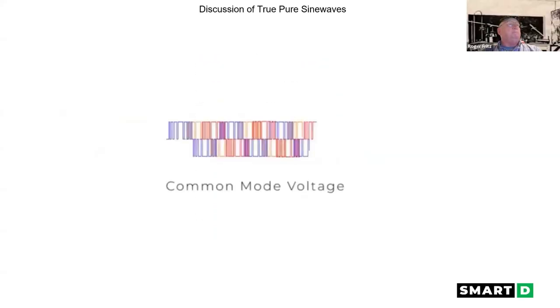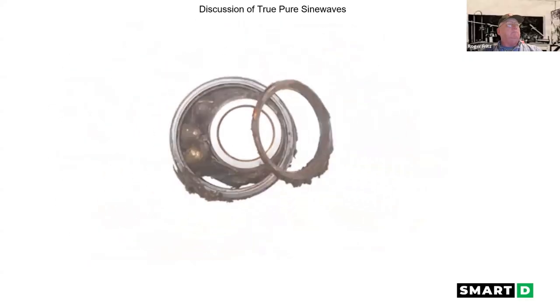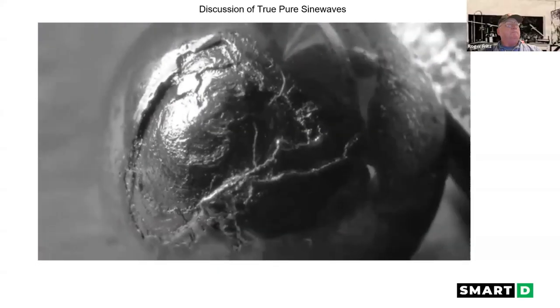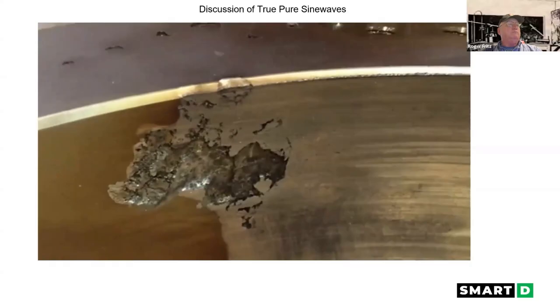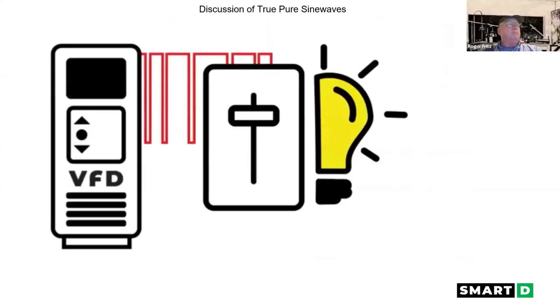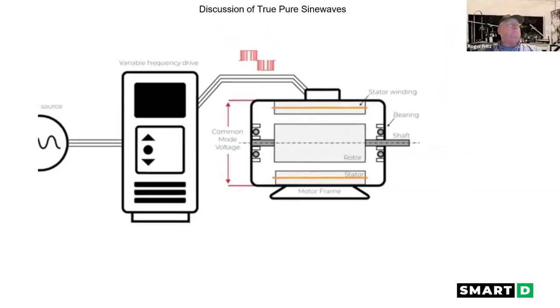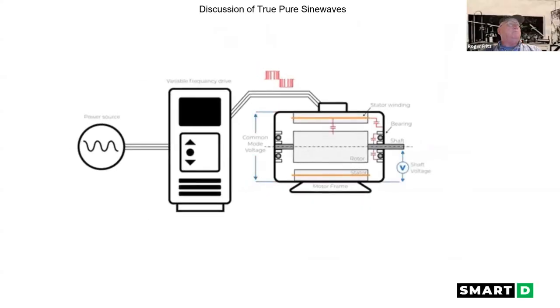Common mode voltage is created by VFDs switching IGBTs on-off continuously. This causes wear and tear on the motor bearings. The first sign of bearing damage is audible noise due to the bearing balls traveling over the pitted and frosted areas. How are these pitted and frosted areas created? Fast switching of the IGBT creates parasitic capacitances in the motor. Common mode voltage and capacitances are sources of a shaft voltage. Shaft voltage causes arcing through the bearing lubricant, which results in pitting on the bearings and fluting on the bearing races.